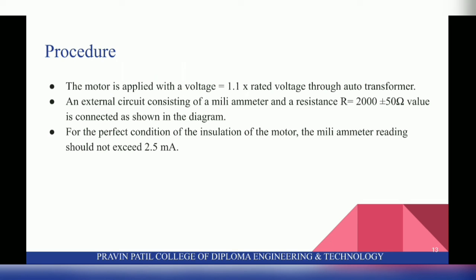So procedure is the motor is applied with a voltage which is equal to 1.1 into rated voltage through auto transformer. An external circuit consisting of a milliammeter and a resistance R is equal to 2000 plus or minus 50 ohm value is connected as shown in the diagram. For the perfect condition of the insulation of the motor, the milliammeter reading should not exceed 2.5 milliampere. So this test is carried out to check the leakage current if there is any.